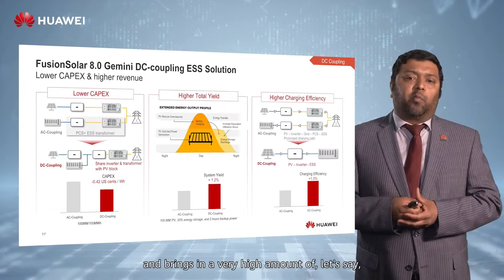When we compare it here, the most challenging thing with the centralized solution is the state of charge, because there are different racks and no possibility to match all the racks. This brings significant differences between racks, causing discharge issues with the centralized solution, all of which is optimized with our solution in the smart string ESS concept.